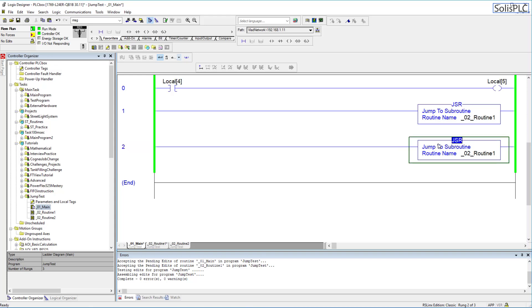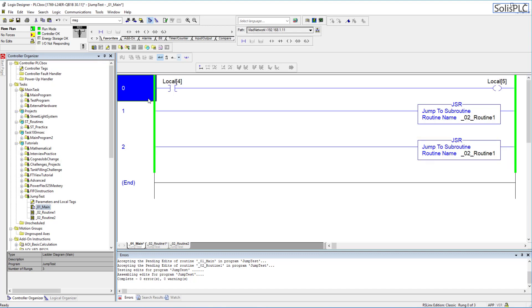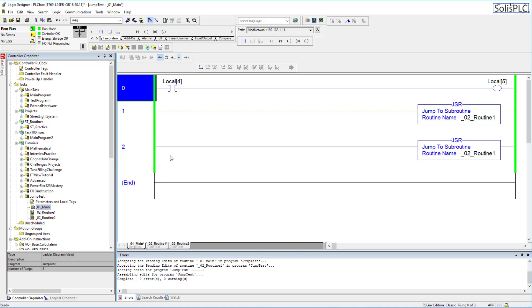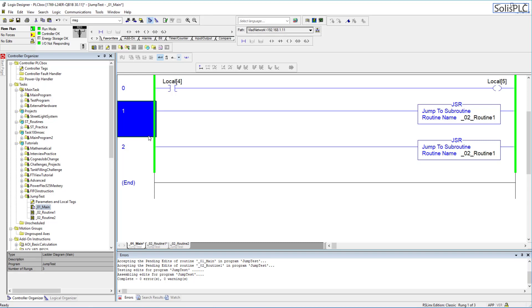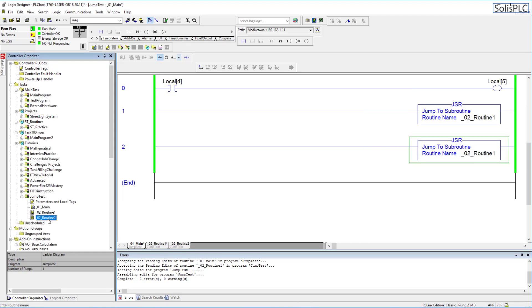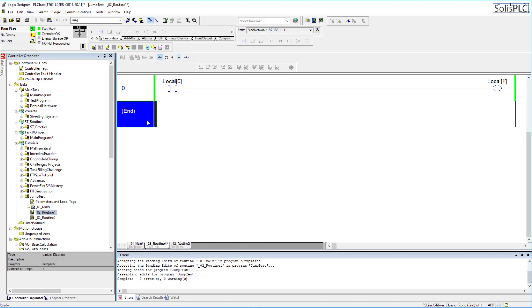Now in this case you'll notice that I have this JSR going back to routine 1 which is obviously something that you shouldn't do in the field but it allows you to do so essentially jumping a second time to routine 1 before completing the main. Now this is something that's very interesting because essentially within a single PLC cycle you're going to execute routine 1 twice. Now that is not something that I advise you to do but you can certainly encounter this practice in the field. That being said what's going to more normally be expected is this is going to be routine 1 and here you'll see routine 2 which is already created at the bottom here. So let's take a look at some of the essentially examples as to how you can recognize if the routine has been or has not been called.